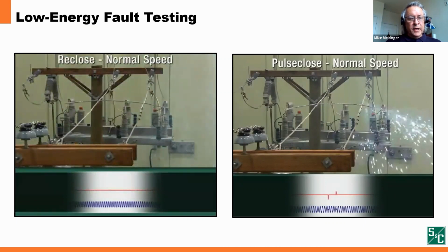See those conductors swaying in the back there? With sufficiently slack conductors, that is essentially what happens as the energy goes through the two phases. The conductors move apart, and if they're slack enough, they relax and move close, could even touch or overcome the air insulation and create another fault upstream.